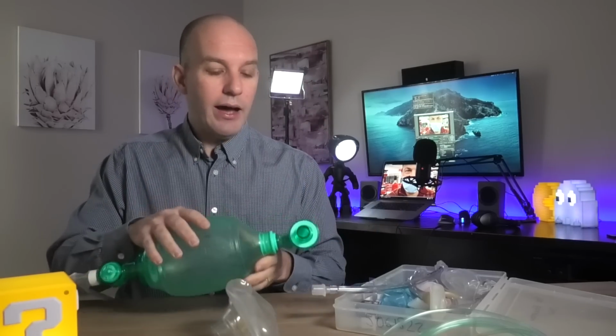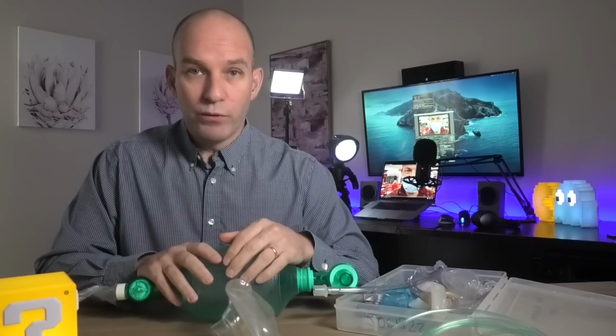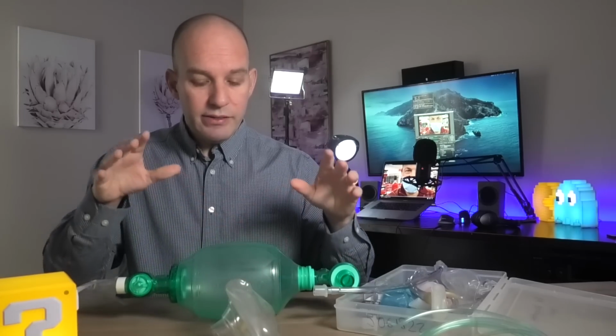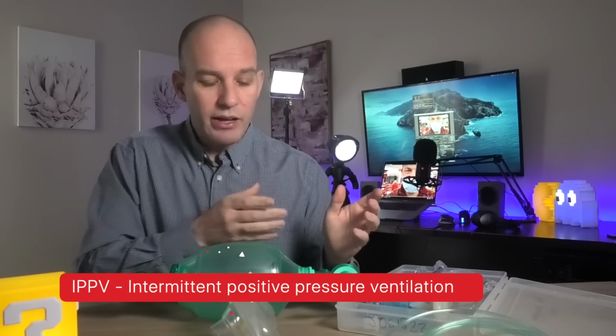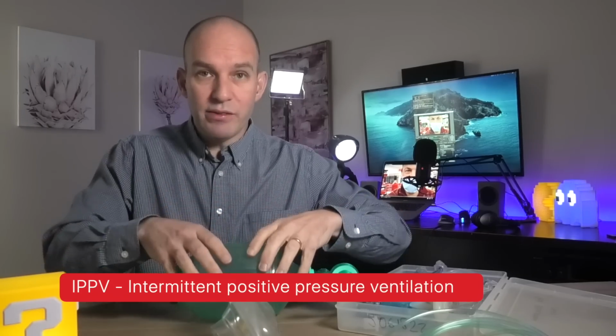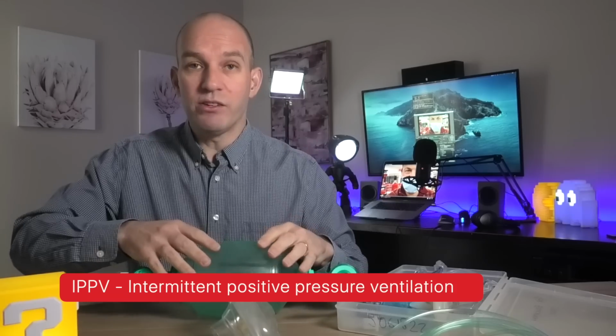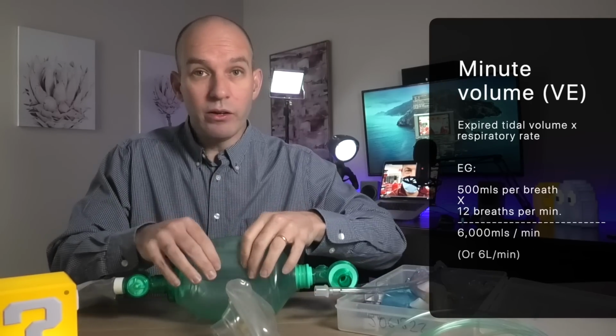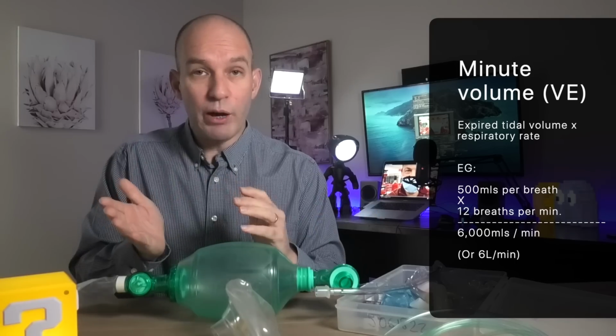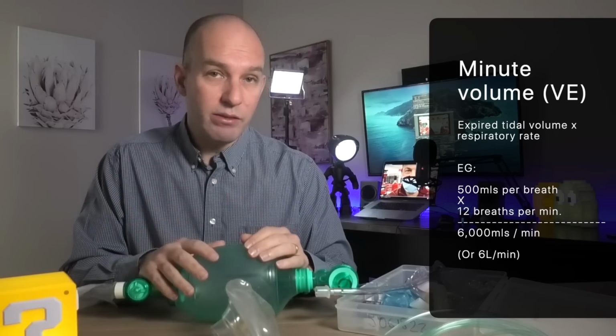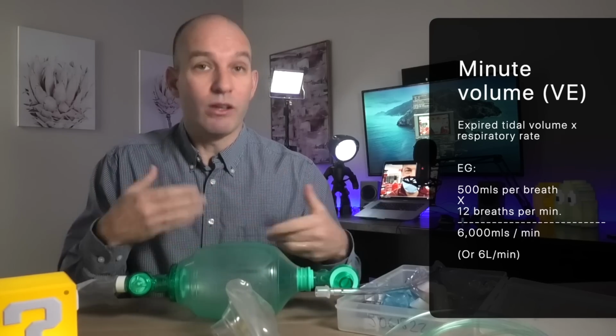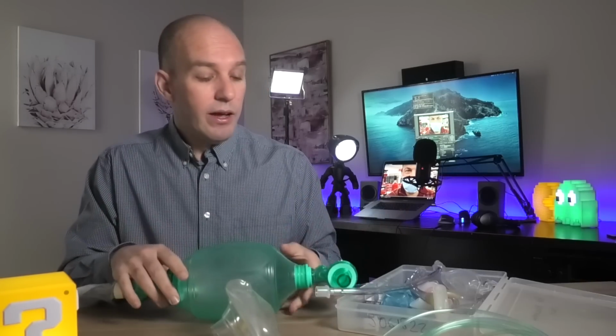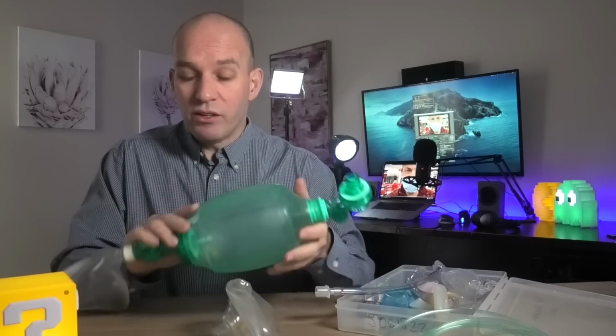Okay, so for that very reason, these things are only good at what we call intermittent positive pressure ventilation, and that is to say that we deliver a set amount of volume to the patient, and we do that 12 times per minute. So if I did a 500 ml breath, and we did it 12 times per minute, that's going to be 6,000 mils or 6 liters of air per minute, which is a normal exchange that we do quite normally by ourselves. But that's all these things can do.